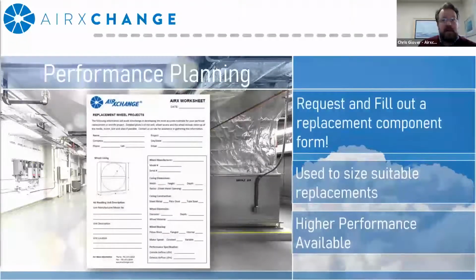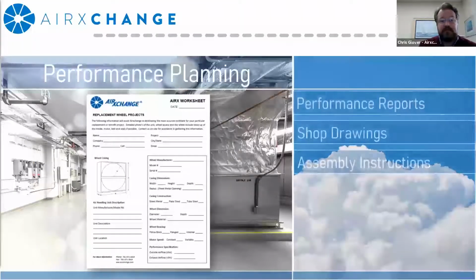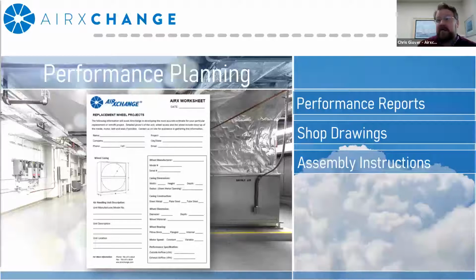So your first step should be requesting and filling out what I call a replacement component form. It's a one-page form, and you basically fill it in with information that should be available just by viewing the components. Just by opening up the cabinet, you should be able to ascertain 90% of what's on this form. And really, this gets us about 95% of the way there when developing a replacement strategy or a repair strategy, depending upon what you have inside the unit. In terms of deliverables, after you send a replacement component form in, what can you receive back? You can expect shop drawings, electrical information, skid dimensions and weights, as well as product assembly and maintenance documentation. This is all going to be pretty vital for you in developing the strategy for replacing or repairing that particular component.